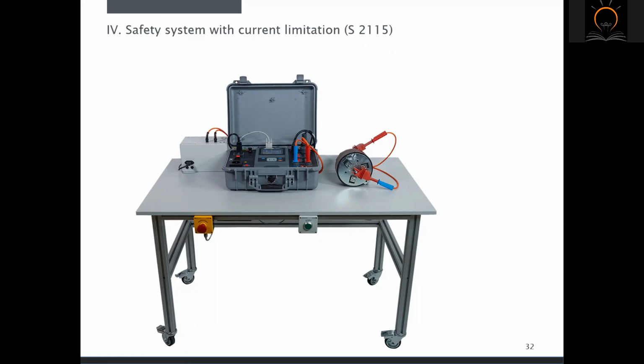Test stations with a current monitoring safety module are intended for production lines where withstanding tests can be performed with low current outputs, under 3 mA. When such a test station is used, the requirements of the standard can be omitted. The operator initiates the test sequence using the external start key. Despite the fact that safety is ensured by the current limit, the test station is additionally protected by a safety button for emergency shutdown.